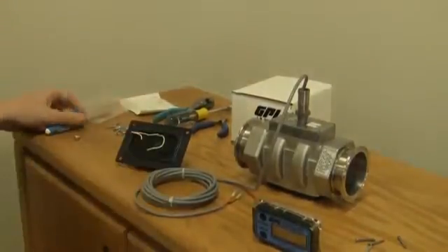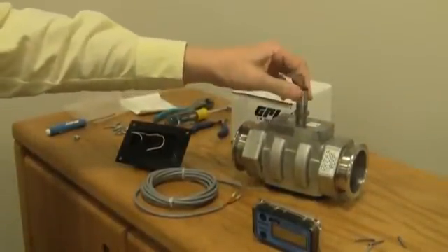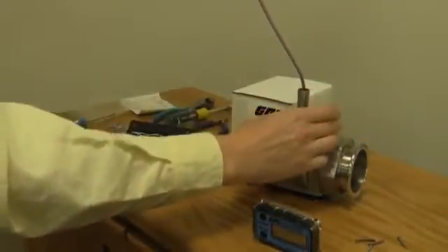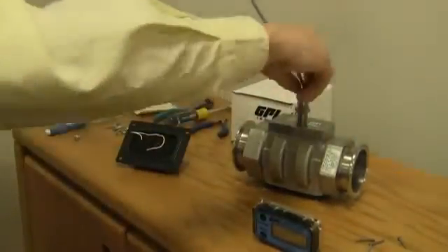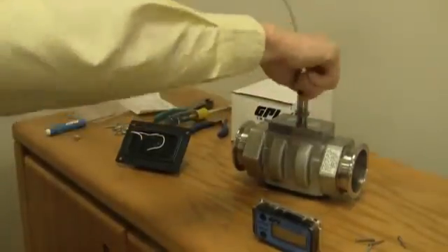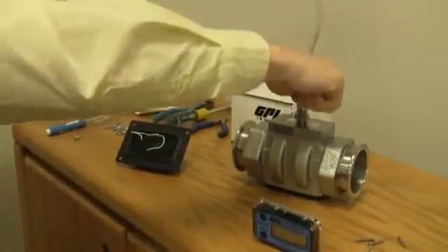Now you notice I got this nice and tight, tightened down, but we don't know how far down it is. You want to make sure this jam nut's pushed up pretty far and then you want to tighten this until it gets snug against the turbine body. You'll be able to feel it, it'll just get there.